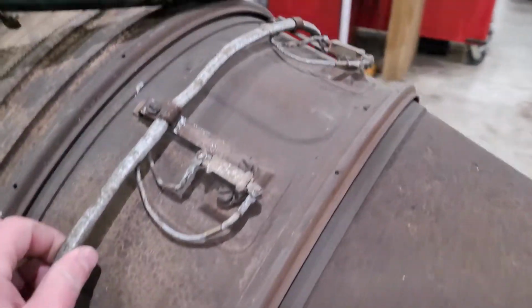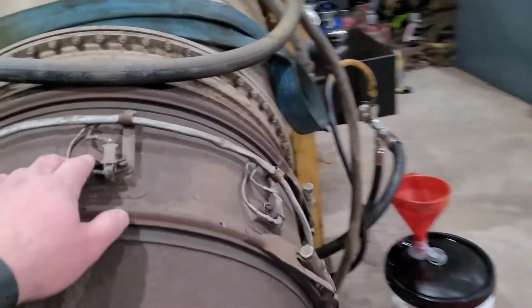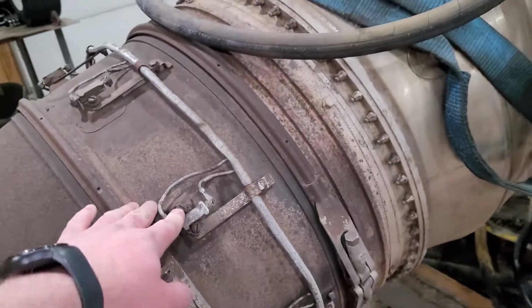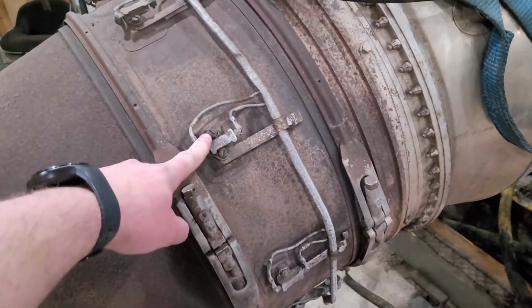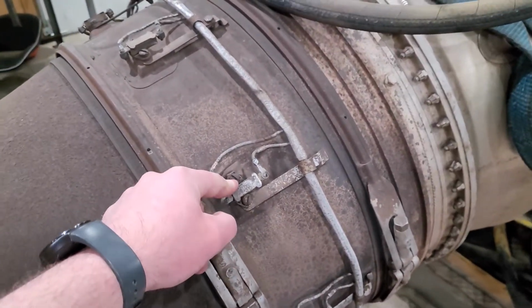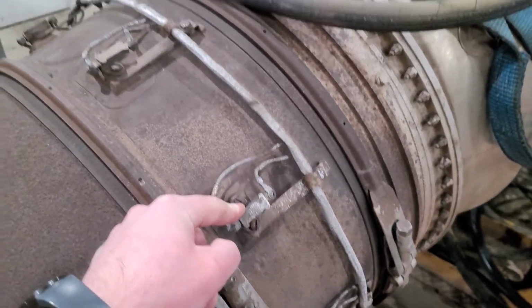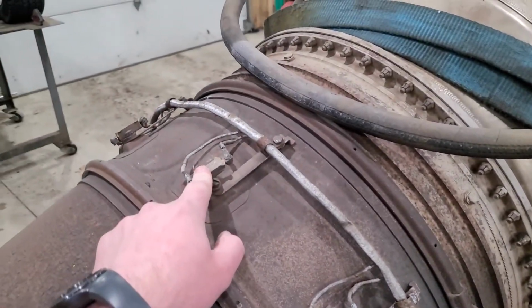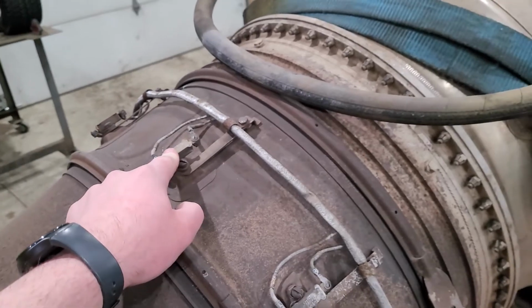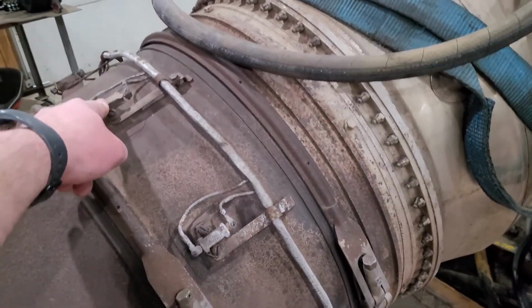We've got a set of thermocouples that will measure the exhaust gas temperature. We'll look in the manual, figure out what type of thermocouples these are and how they're wired. We'll be able to test the whole circuit to make sure these still work so we get an accurate exhaust gas temperature reading.